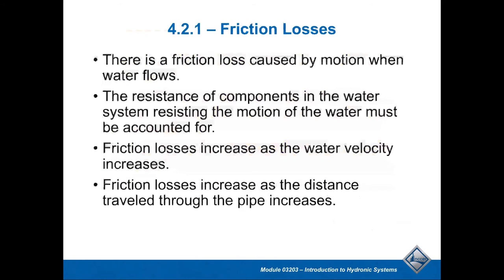Why do we have friction loss? What determines the friction loss rate of a system is the flow — the more flow you have, the higher the friction loss rate. This is really based on the second pump law, where the pressure drop changes by the square of the GPM percentage change. So if you double the flow rate, your pressure drop will go up by two squared — four times. The more velocity, the higher the flow rate; the higher the flow rate, the higher the pressure drop.